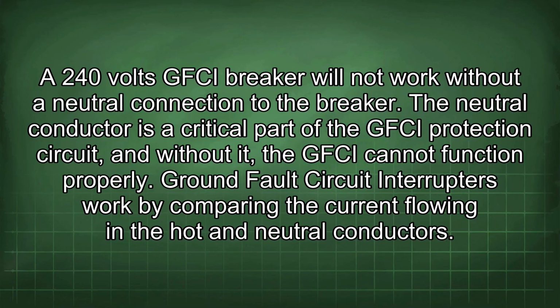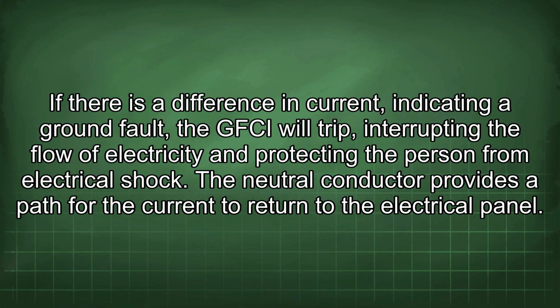A 240 volts GFCI breaker will not work without a neutral connection to the breaker. The neutral conductor is a critical part of the GFCI protection circuit, and without it, the GFCI cannot function properly. Ground fault circuit interrupters work by comparing the current flowing in the hot and neutral conductors. If there is a difference in current, indicating a ground fault, the GFCI will trip, interrupting the flow of electricity and protecting the person from electrical shock.